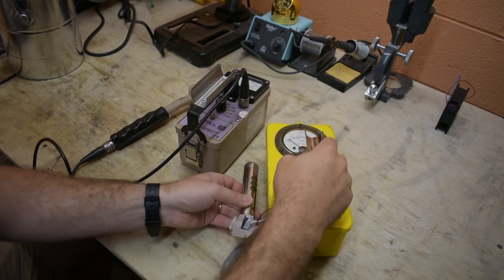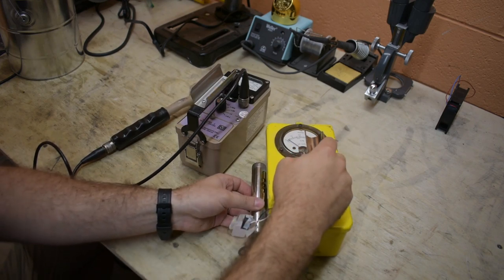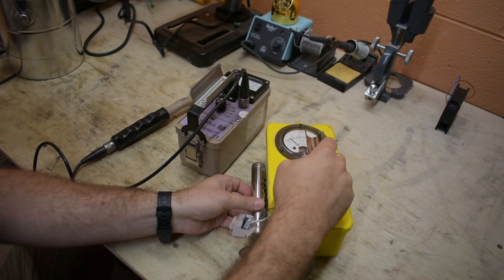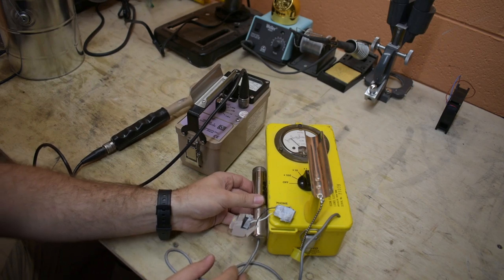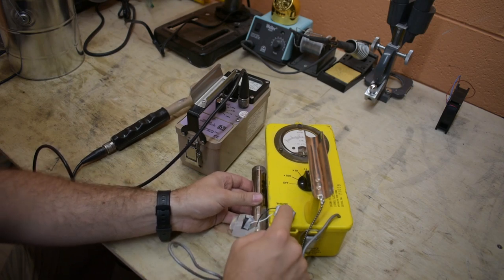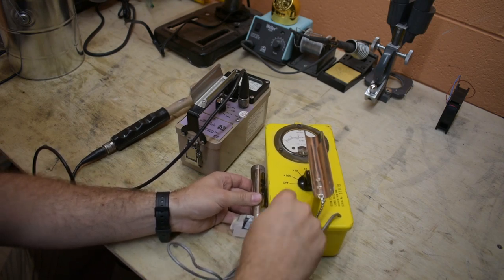So you can see this check source gives off beta radiation because with the window closed it can't detect it. If you open up the window it can once again detect it.